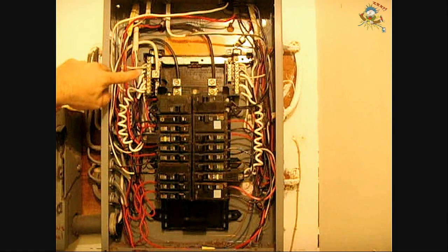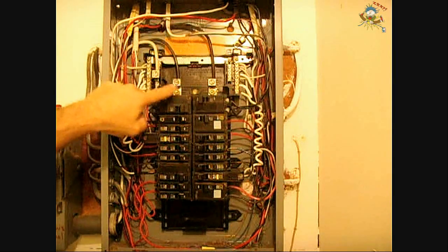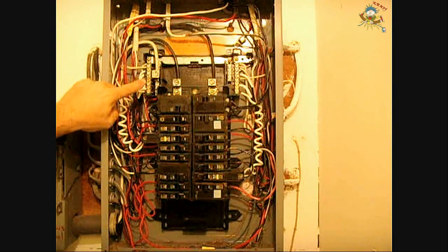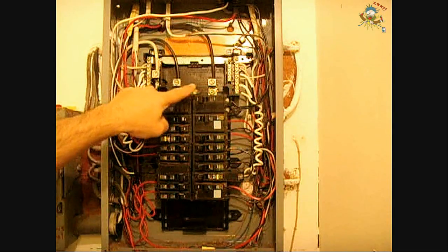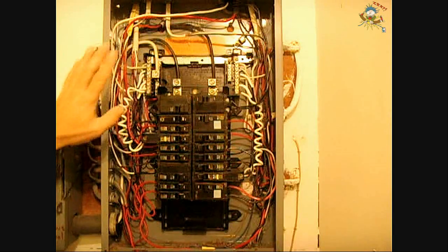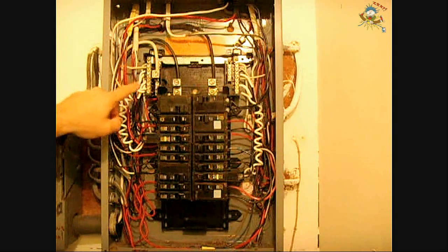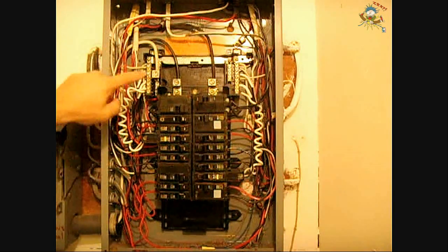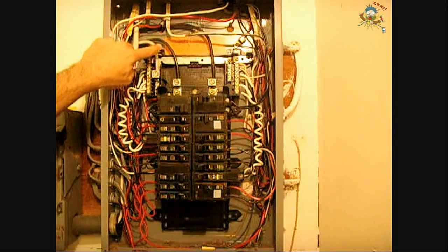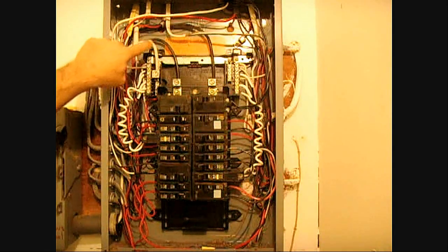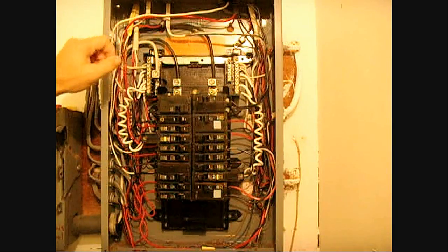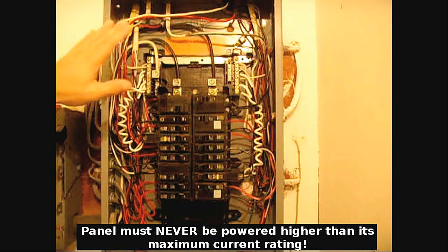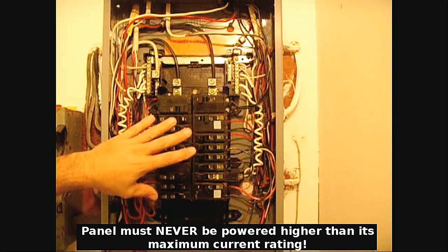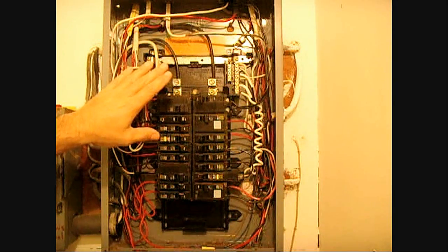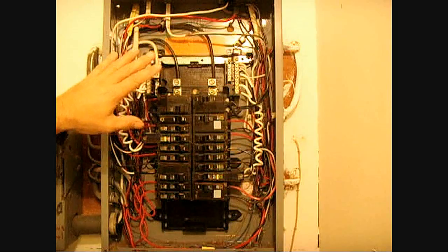Your neutral wire coming in is usually the same size as your hot feeds, or it could be one size smaller. There's not a problem there. As long as you see that these are properly rated, and if that's one size less, you're okay. So if this was a 200 amp panel, you would want to read the writing on this copper wire. If it's copper, make sure it says 2/0, which means 2-aught, then you know you have the right size wire for the panel. That wire is capable of handling 200 amps as a service conductor.